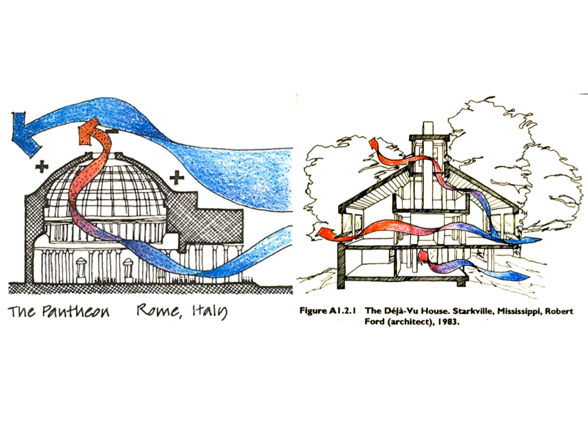Stack ventilation works on the buoyancy or stack effect. As the building gains heat from conduction, solar radiation, lights, people, and equipment, the indoor air warms up and rises. If there's a place for it to exit, it sucks in cooler outdoor air at the bottom, and that cycle continues.